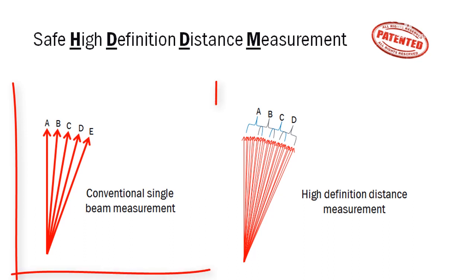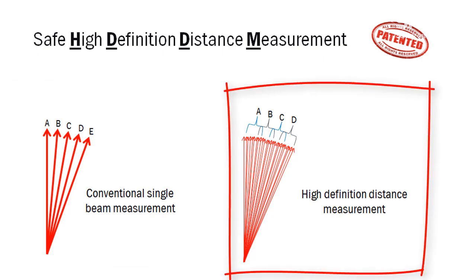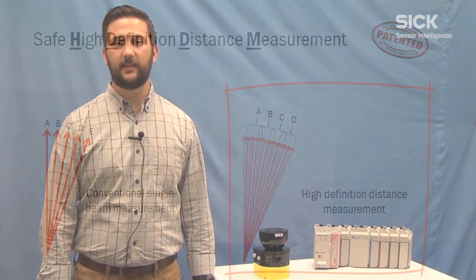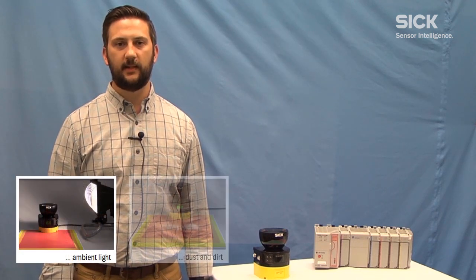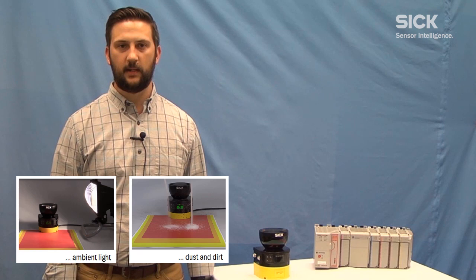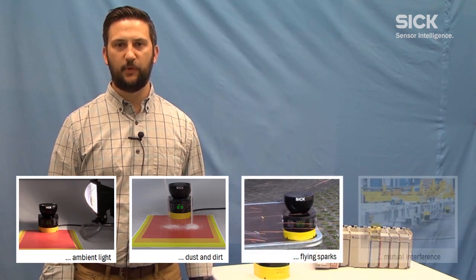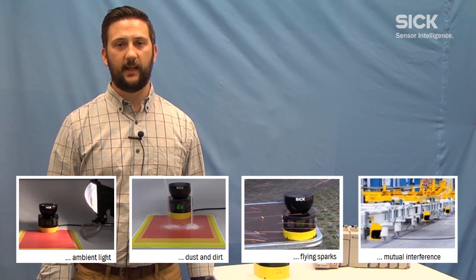Most scanners use a conventional single beam measurement principle which generates 500 pulses per scan. Safe HDDM generates more than 80,000 pulses per scan. This additional data combined with intelligent algorithms that are built into the scanner results in much more reliable scanner performance. It enables the microScan3 to be highly resistant to things such as ambient light, dust and dirt in the air and on the screen, flying sparks, and mutual interference. This means less downtime and higher productivity.